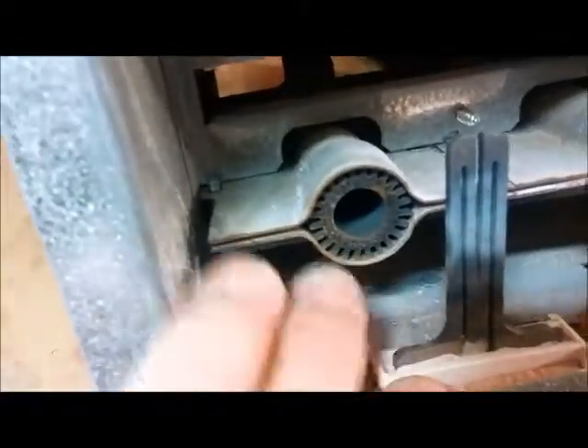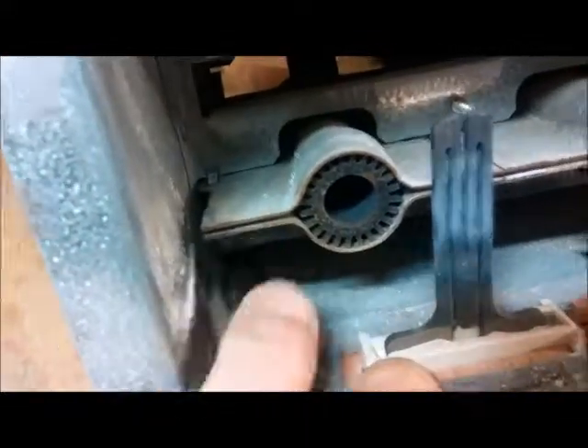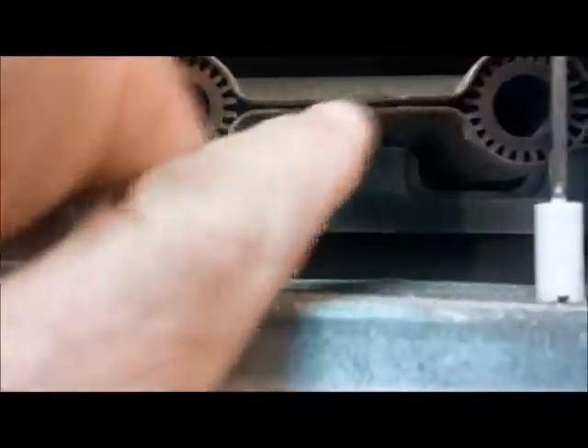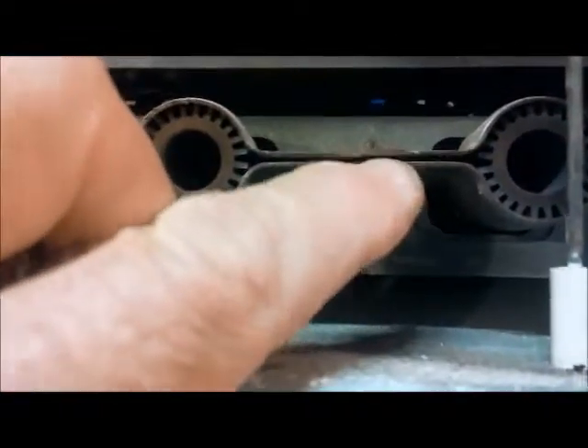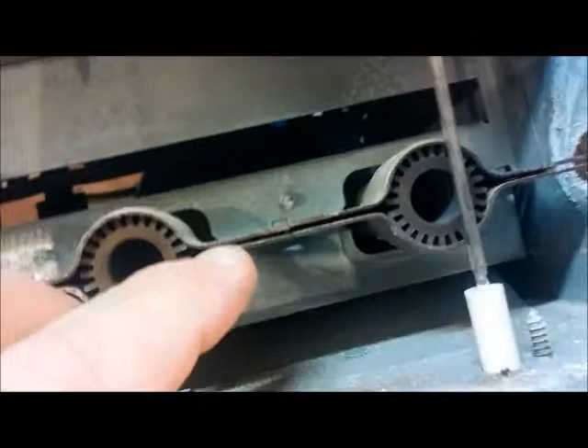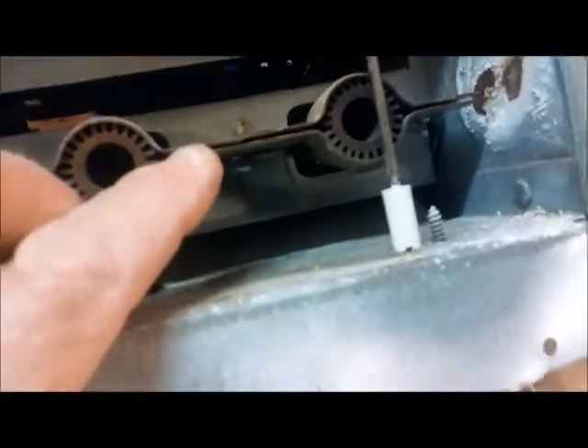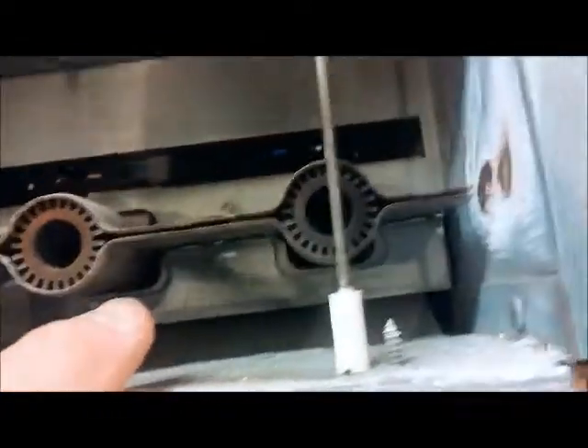Burners need to be lined up perfectly if you ever take them out and clean them. These ones are getting to be a little mucked up here. So if that crossover, say we're getting a, sometimes this is so mucked up with rust in here that they will not cross over. So you need to pull them out and get a wire brush on them and clean them up. Otherwise, that's going to cause a flame current fault.